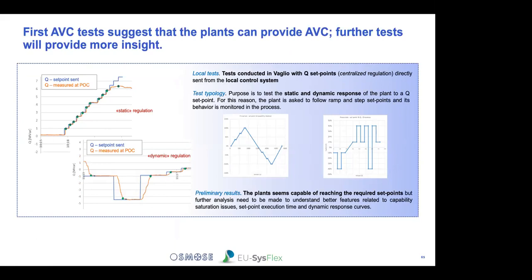We're talking about static and dynamic regulation. For the static case, the set point is varied slowly, so we want to assess if the plant is capable of actually reaching that set point with a certain precision. Dynamic regulation is more of a stepwise change in reactive power, and then we will also test the voltage set point reaction and see how dynamically the power plant will respond.